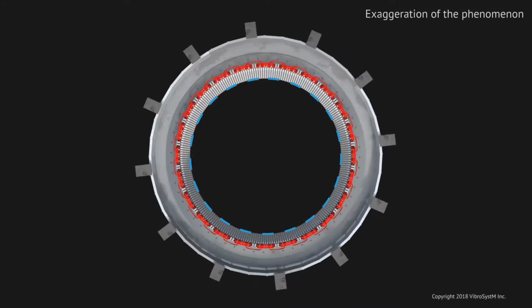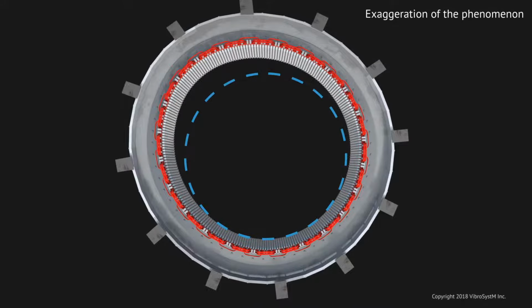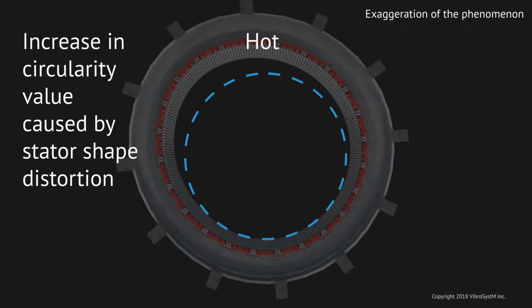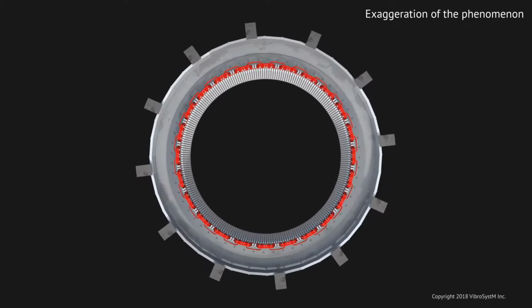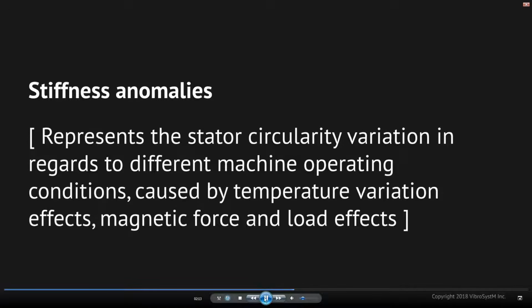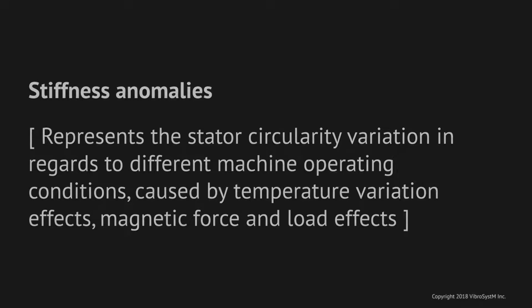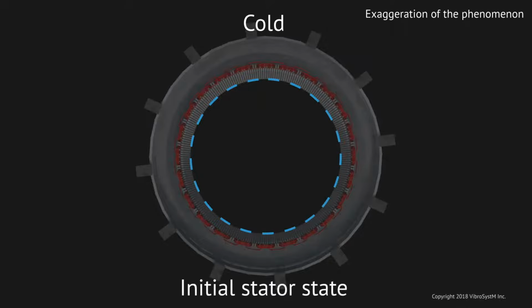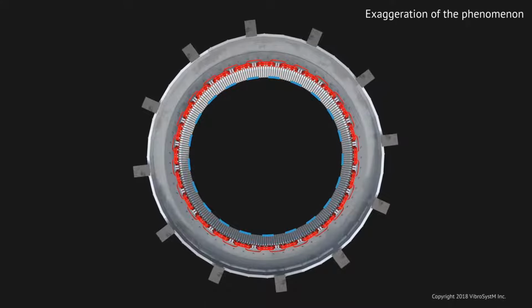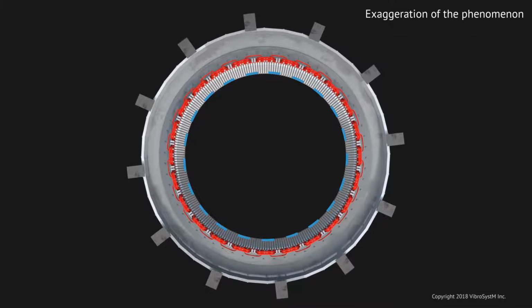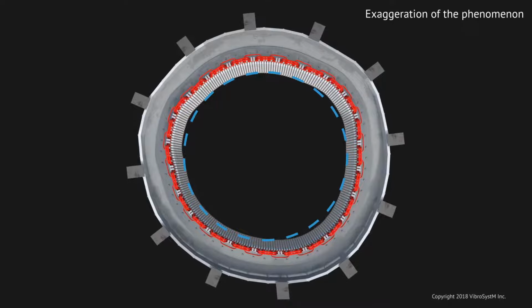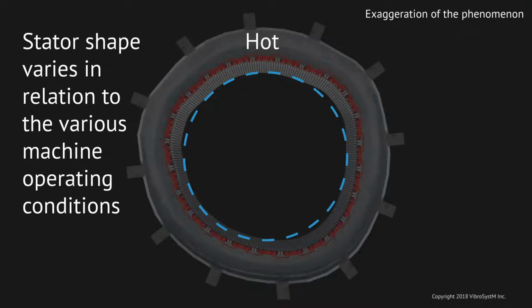Okay, so you have an initial stator state, which is perfectly round, and as you heat it up, as you excite the rotor, as you synchronize the unit, you introduce a whole bunch of forces, and that can, and usually does, influence greatly the actual end result of the stator shape. Stiffness anomalies represents the stator circularity variation in regards to different operating conditions caused, again, by temperature variations, magnetic force, and load effects. So again, initial stator state, which is round, and it will start deviating. It expands, and it can deviate because of these different forces. You can see sometimes at a certain load, you'll start seeing some creeping, and distortions will appear, telling you that the expansion is not symmetrical, and you need to check sole plates, you need to check core to frame attachments, different components that need to be verified.